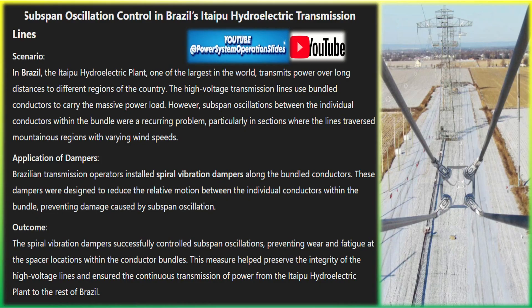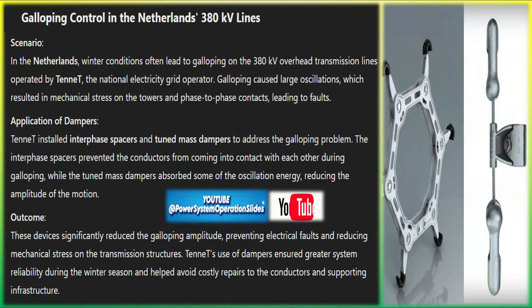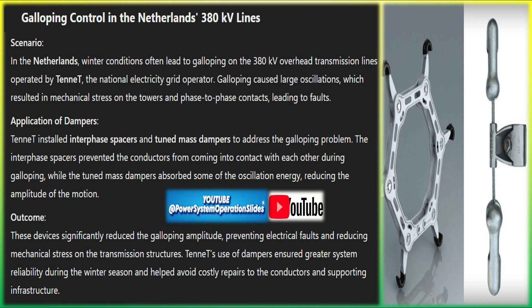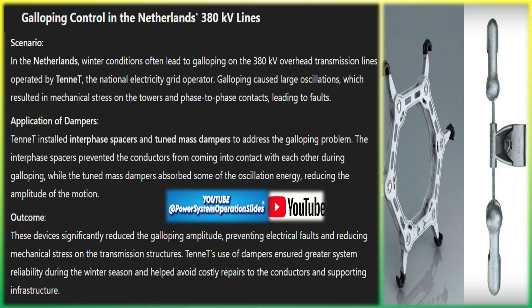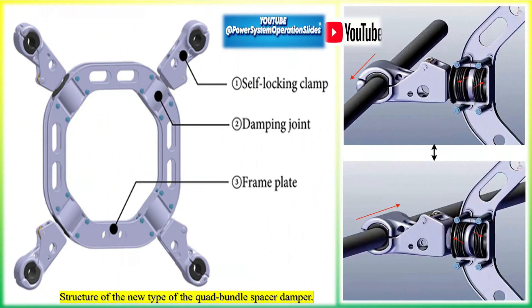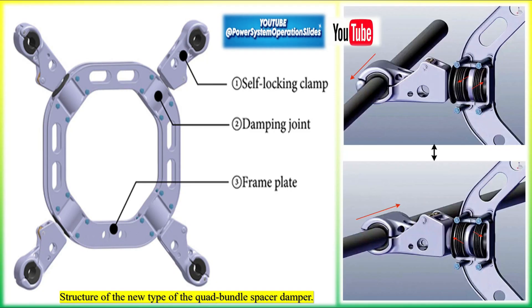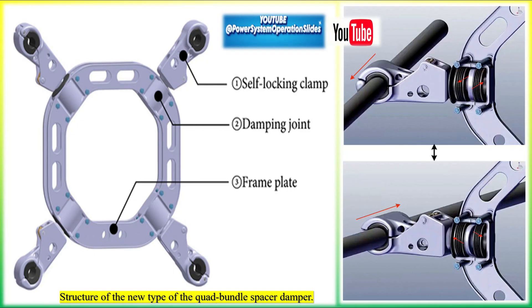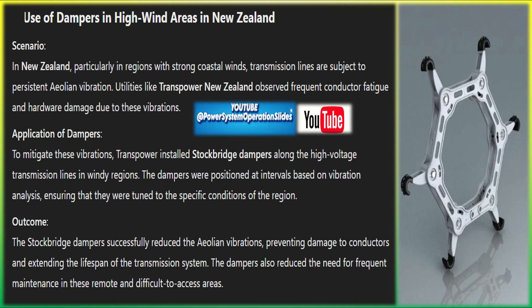While dampers provide significant benefits, their proper installation and tuning are crucial for optimal performance. Dampers need to be strategically placed along the span, typically near suspension points or areas where vibrations are most intense — improper placement can reduce their effectiveness. Different span lengths and line tensions require dampers tuned to specific vibration frequencies; Stockbridge dampers, for example, are designed for specific ranges of vibration frequencies. Environmental factors such as wind speed, temperature, and the presence of ice all affect the type and severity of vibration, so understanding local conditions is key to selecting the right damper.